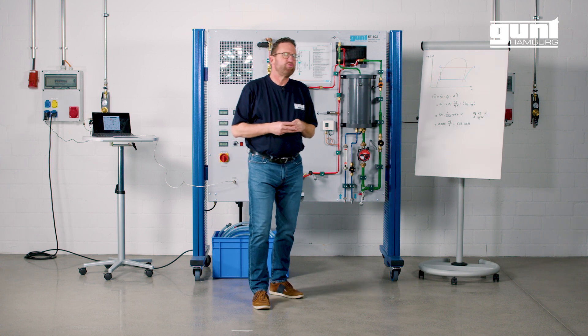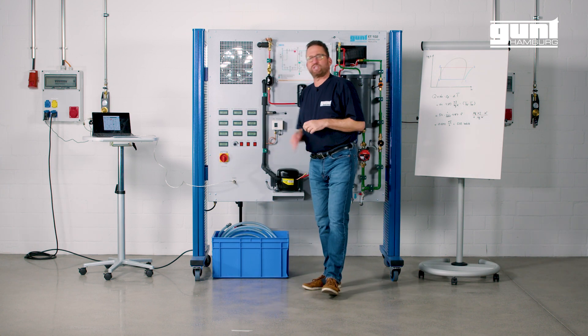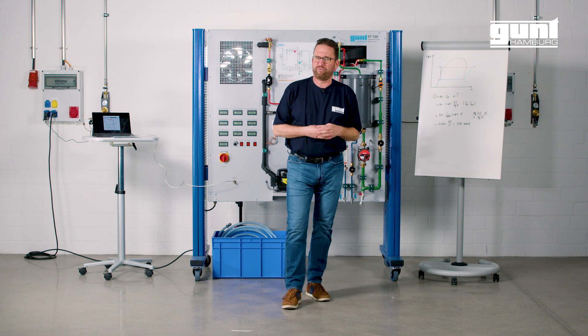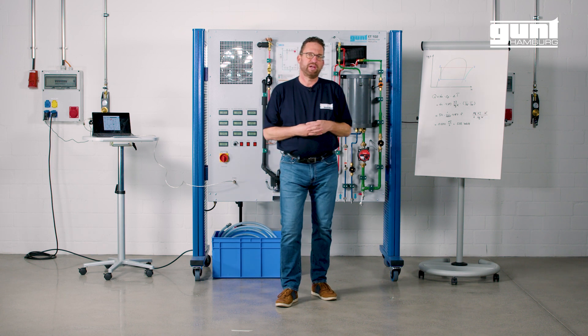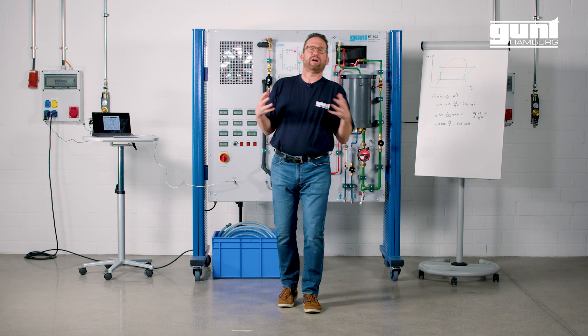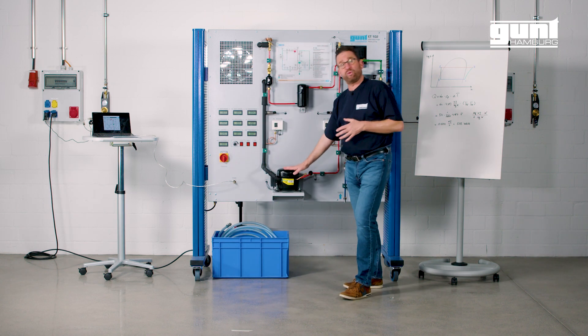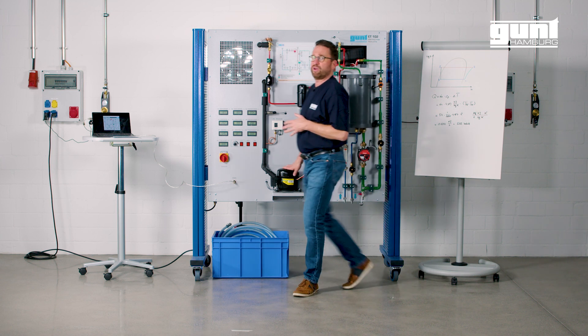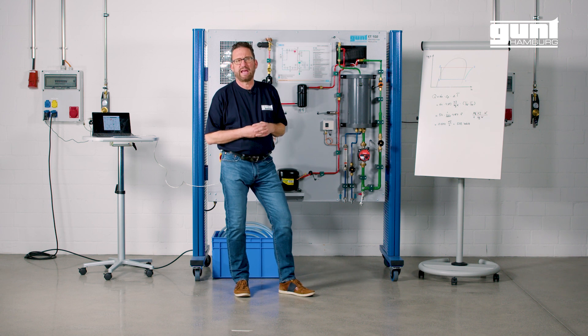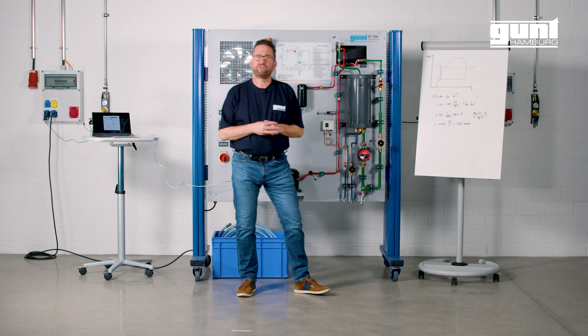The ratio between the heat discharge and the power input is called coefficient of performance, or seasonal coefficient of performance. For commercial heat pumps, the COP or SCOP can reach values of up to 4.5. In other words, for every kilowatt hour of electric power input we get 4.5 kilowatts of heating output, all through the magic of the refrigeration process.